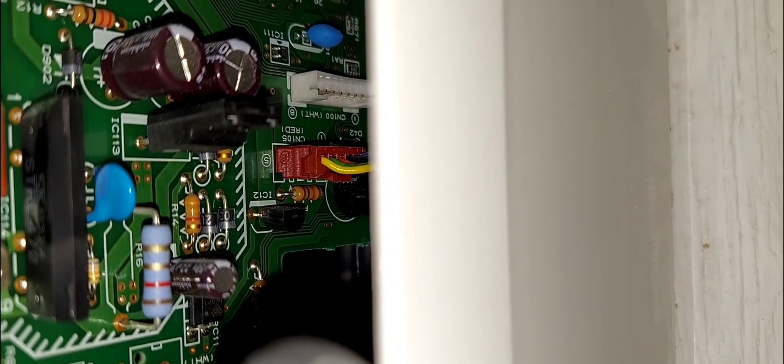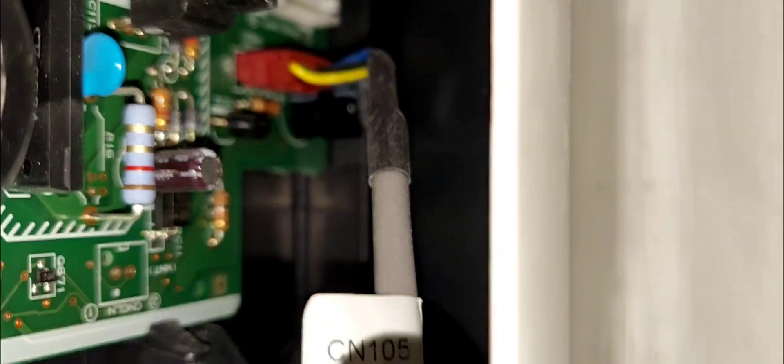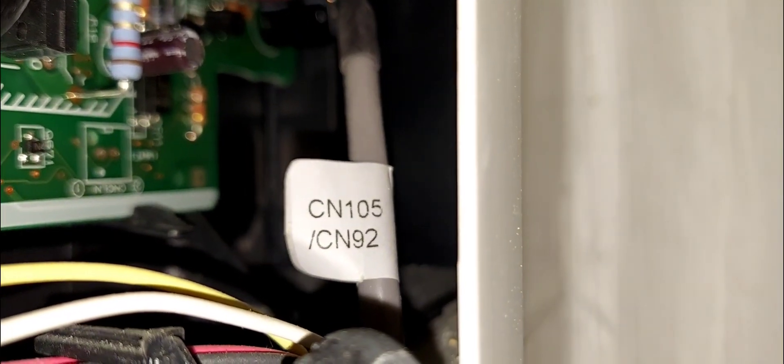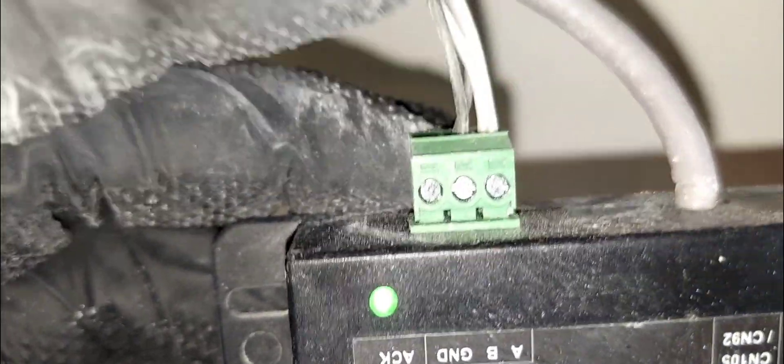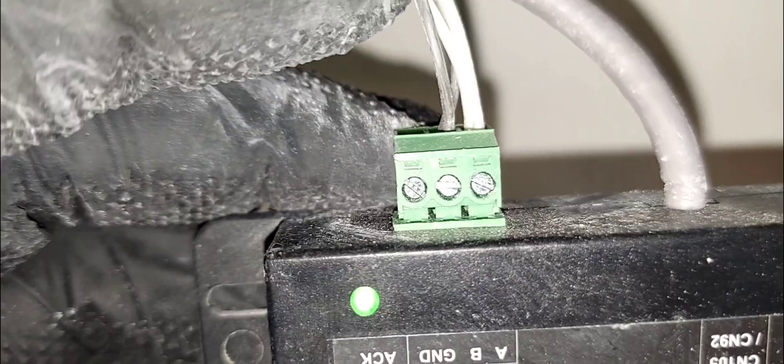You see where it plugs into the board - the red connector CN105. The wire is going to be either CN105 or CN92. In this case it's 105. This is your wire - RS485 - going back to your BMS system. This is going to be a shielded wire. Pretty straightforward.